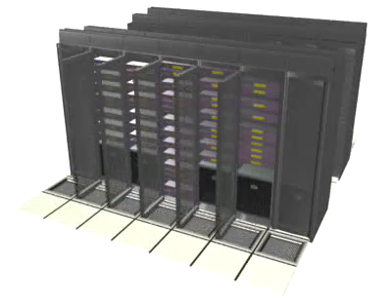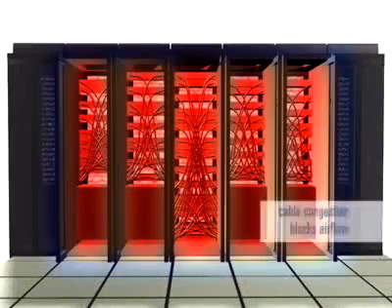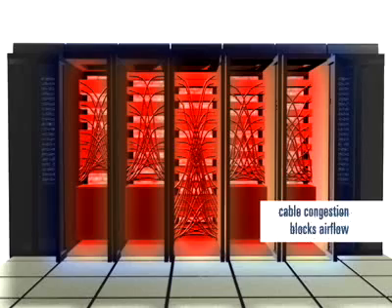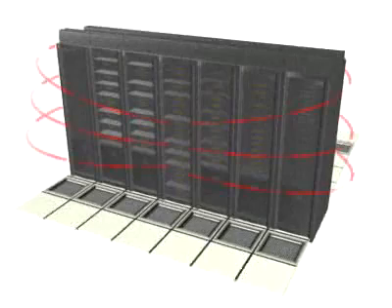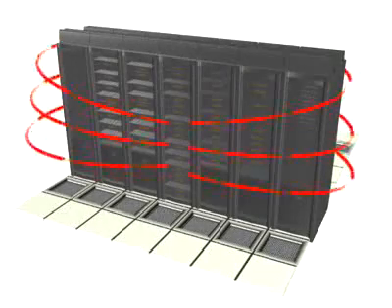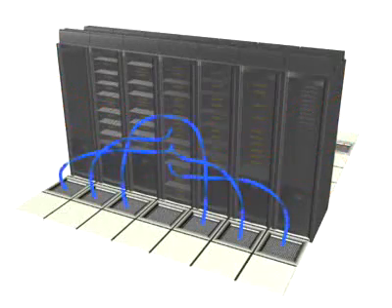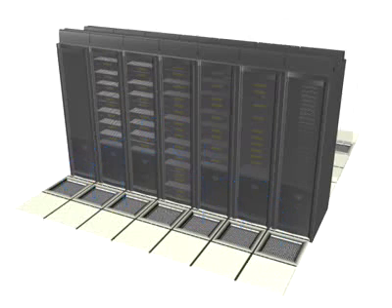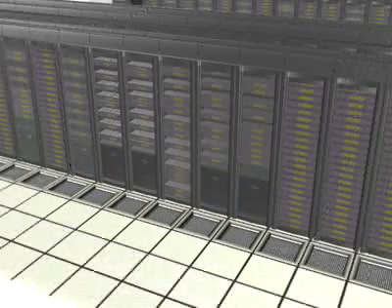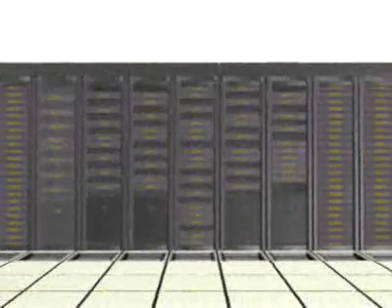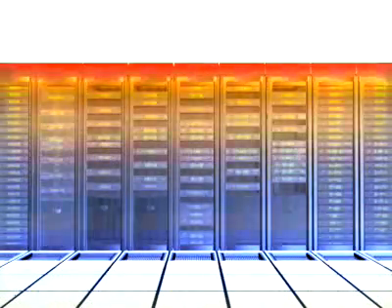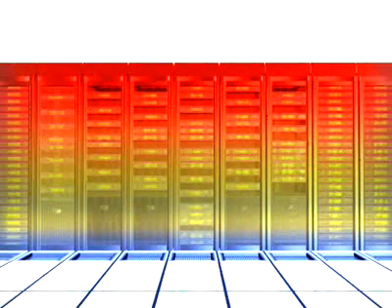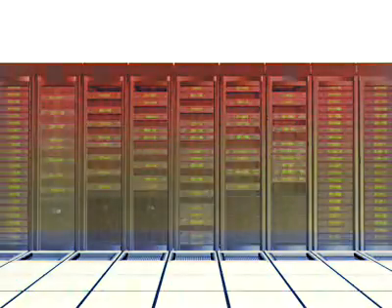6 months later, and it's time for another IT refresh. Even more equipment is added, leading to higher power densities as well as cable congestion from additional network drops and power cords. Air recirculation increases. Because the new, denser servers cannot draw the necessary airflow from the raised flooring for proper cooling, they must pull the required air from another source. The air temperature across the entire room also begins to rise. As more heat is generated, the curtain of hot air at the top of the room is lowered closer to the rack inlet. The cooling situation in the data center becomes critical.